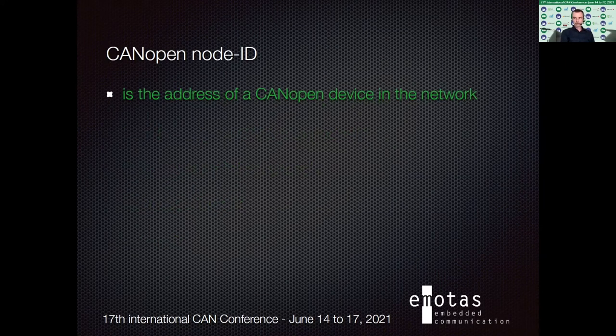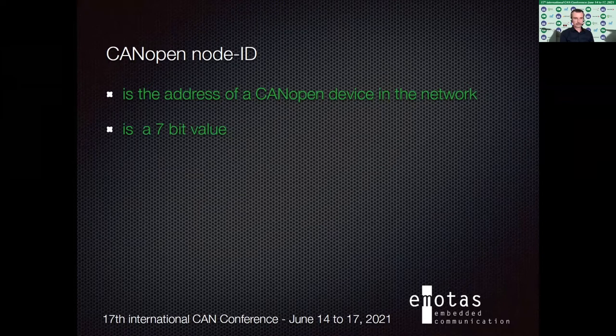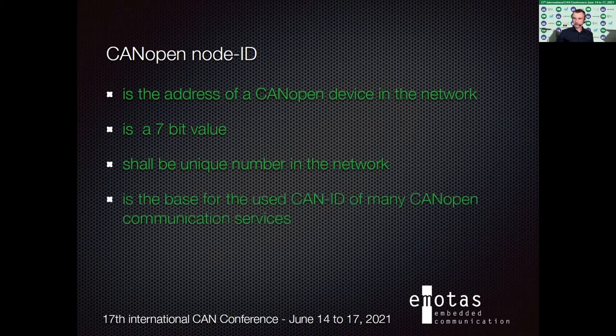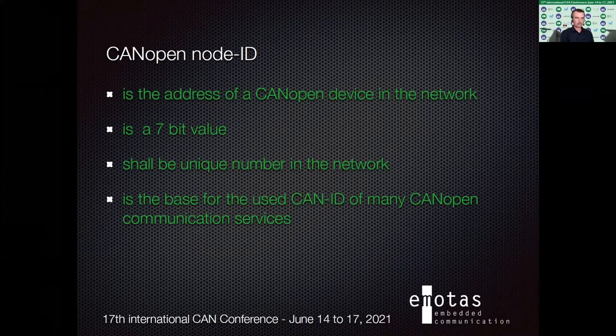A CAN open Node-ID is actually the address of a CAN open device in the network. It has to be unique in the network, and it is a 7-bit value, which means the Node-ID can only go up to the number 127 and starts at number one — so zero is forbidden. You can only have 127 devices in one network. The Node-ID must be unique because many of the services in CAN open use this Node-ID to create the CAN identifier for communication. For example, the error control mechanism uses the CAN ID 0x700 plus the Node-ID of the device sending the heartbeat.